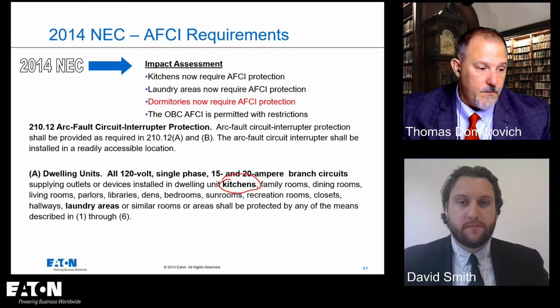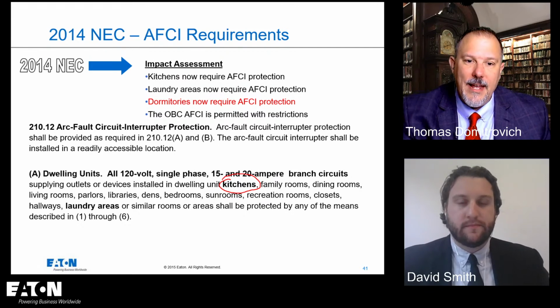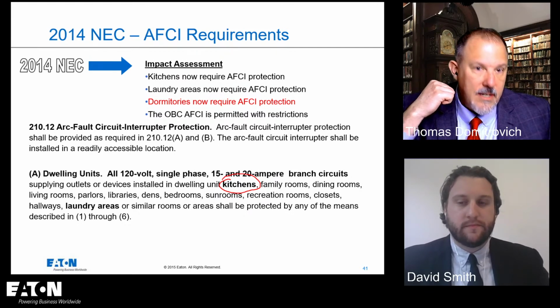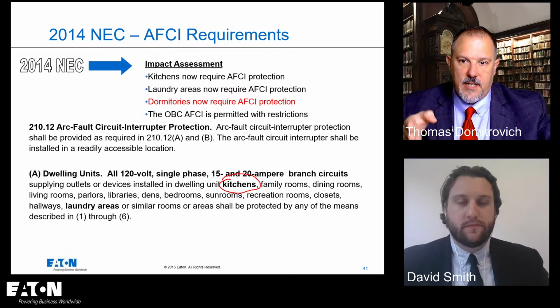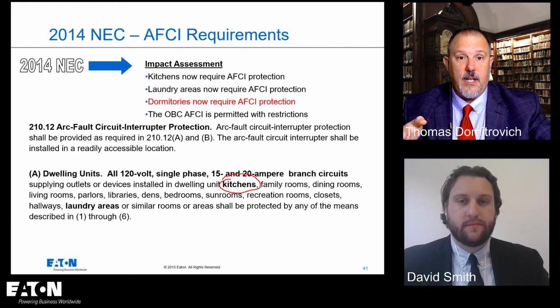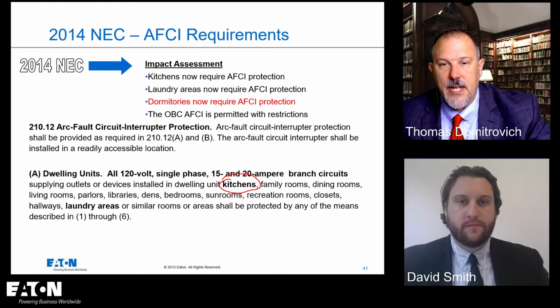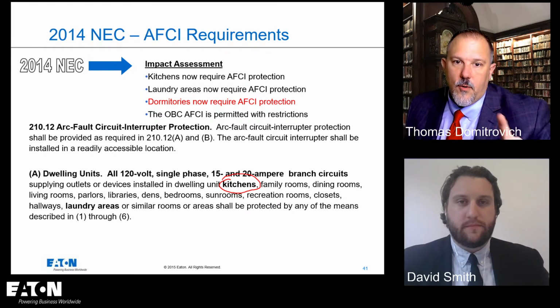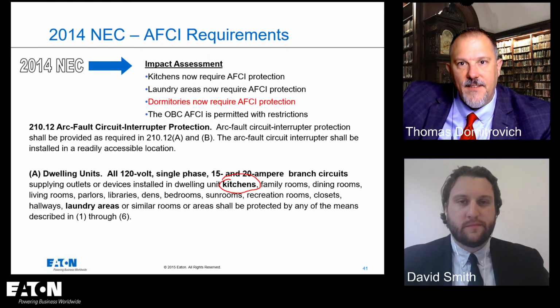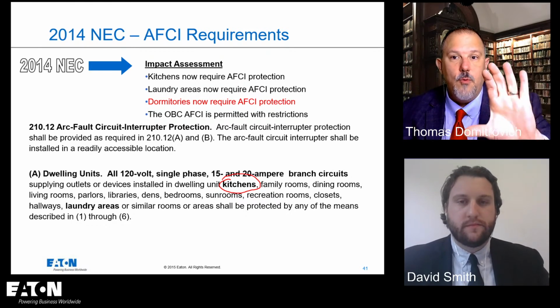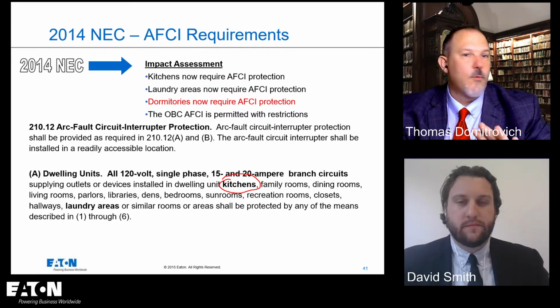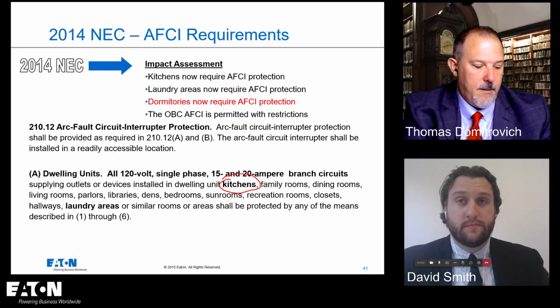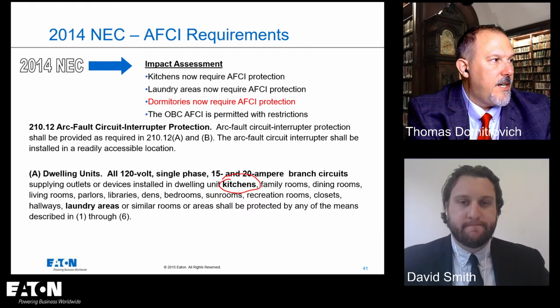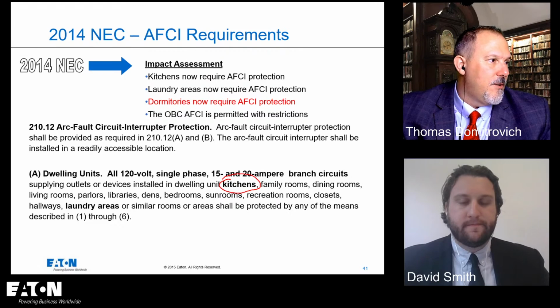And I commend the manufacturer who did that, because they put a lot of information out there that says, look, this stuff will fail. Now, how do you handle a refrigerator that's within 6 foot of the sink, right? The receptacle that's within 6 foot of the sink, and I have to AFCI and GFCI protect it, and all of that protection has to be readily accessible. Right. So one way to do that, I could put AFCI protection in my circuit breaker. I can take that branch circuit down to what they call a blank-faced receptacle. And we make these. Blank face GFCI. I call it a blank face. I don't know if that's right.